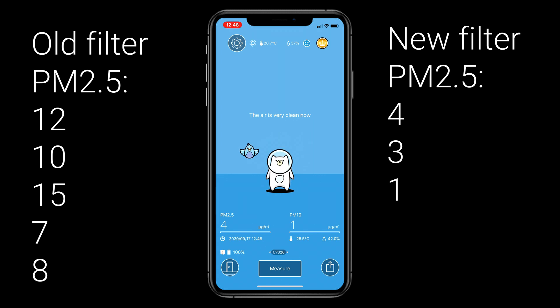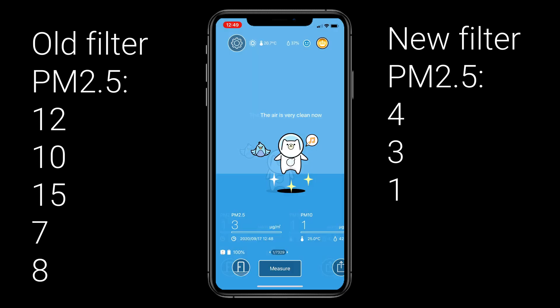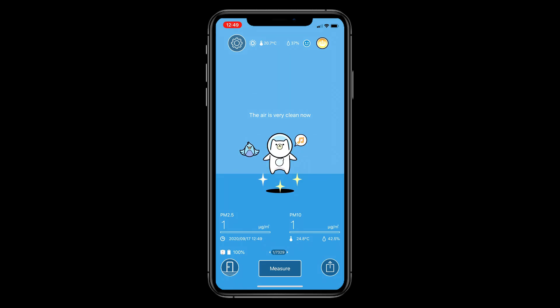I'm going to go ahead and move it and run another test. We actually hit a one in one! So yeah, maybe you do need to change your MERV 16 filter about once a year. I'm not talking about the real thin filters that you should change every month, but these heavy-duty, expensive ones — maybe they do require changing once a year. I'm getting lower numbers: four, three, and now one, taken around the house similar to where I measured before.